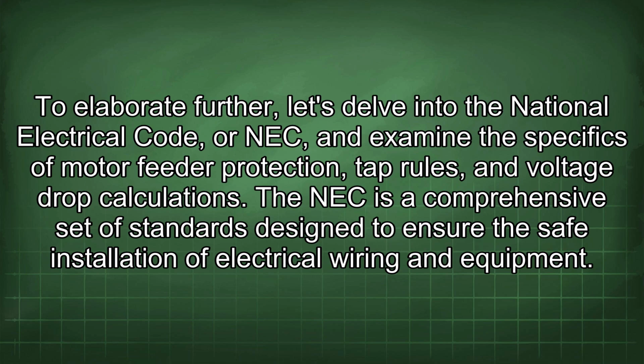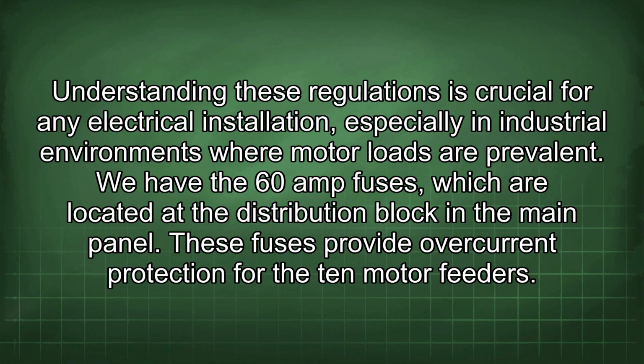The NEC is a comprehensive set of standards designed to ensure the safe installation of electrical wiring and equipment. Understanding these regulations is crucial for any electrical installation, especially in industrial environments where motor loads are prevalent. We have the 60 amp fuses, which are located at the distribution block in the main panel. These fuses provide overcurrent protection for the 10 motor feeders.